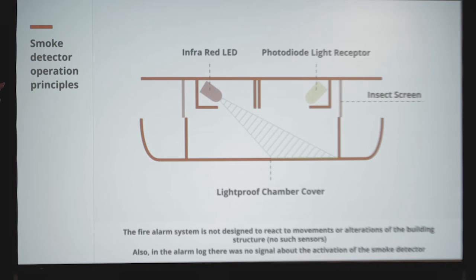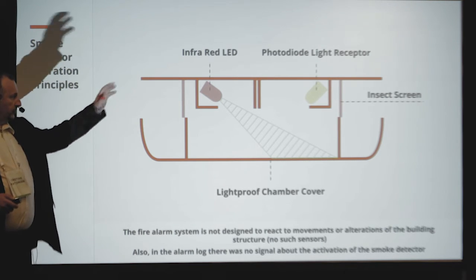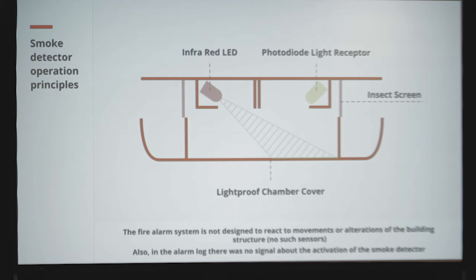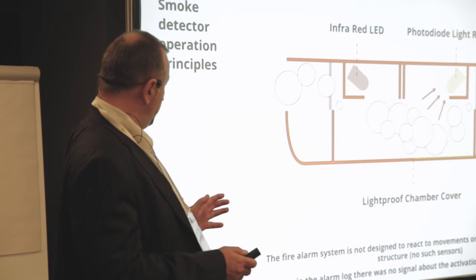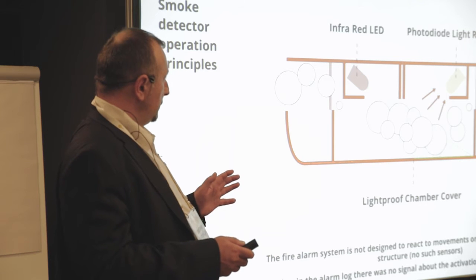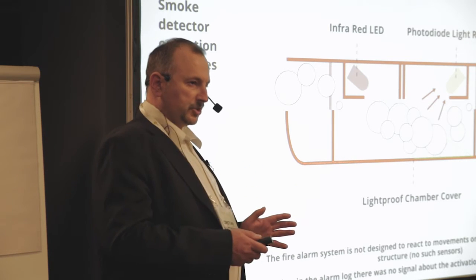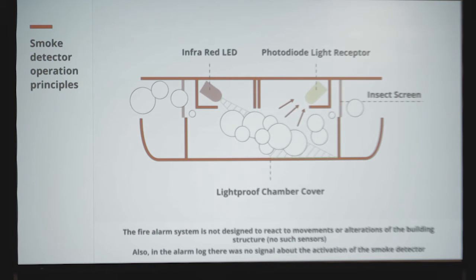We've got here an infrared LED, which constantly sends light to a chamber cover. Normally the photodiode light receptor doesn't get any signal from there. Only if smoke comes inside such a detector, the particles reflect the beamed light, and because of this change of direction by the particles, the photodiode light receptor gets a signal, and in this case a fire alarm is sent to the control unit.